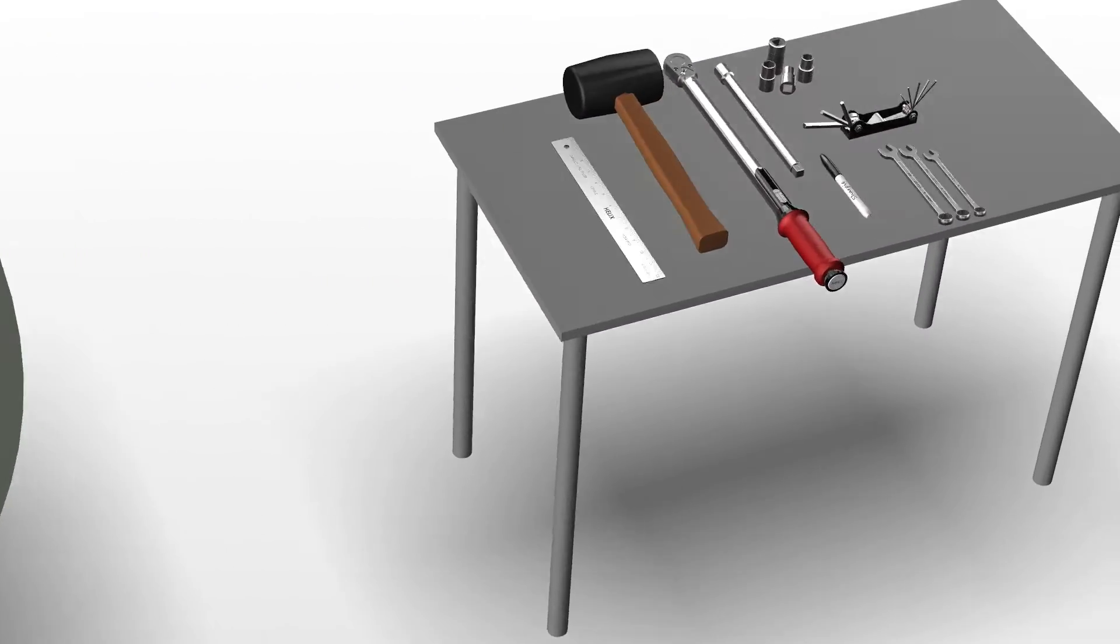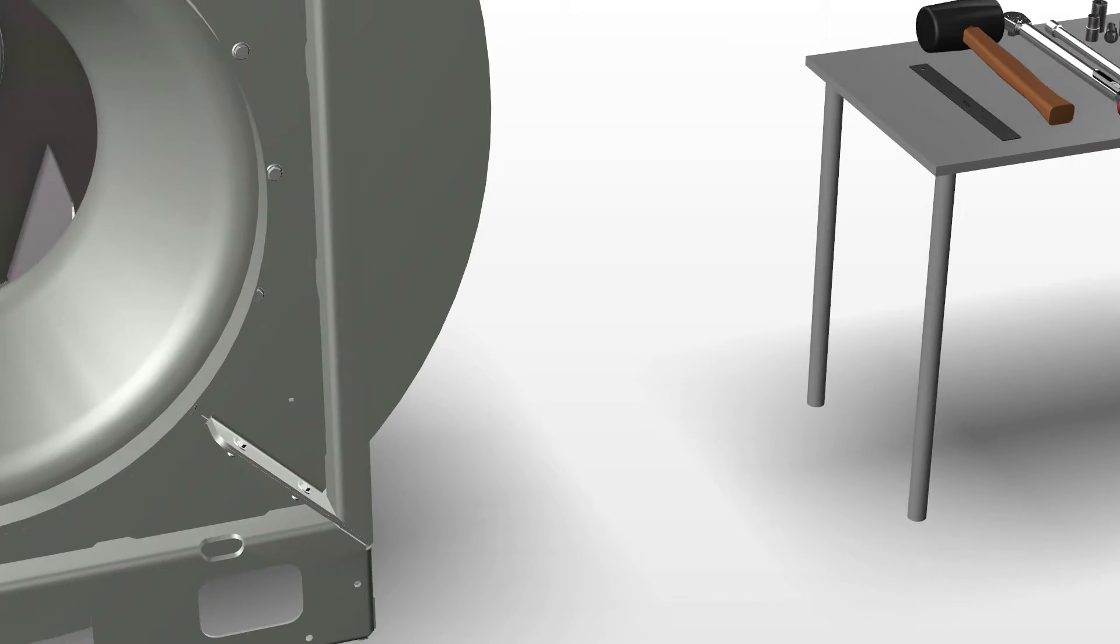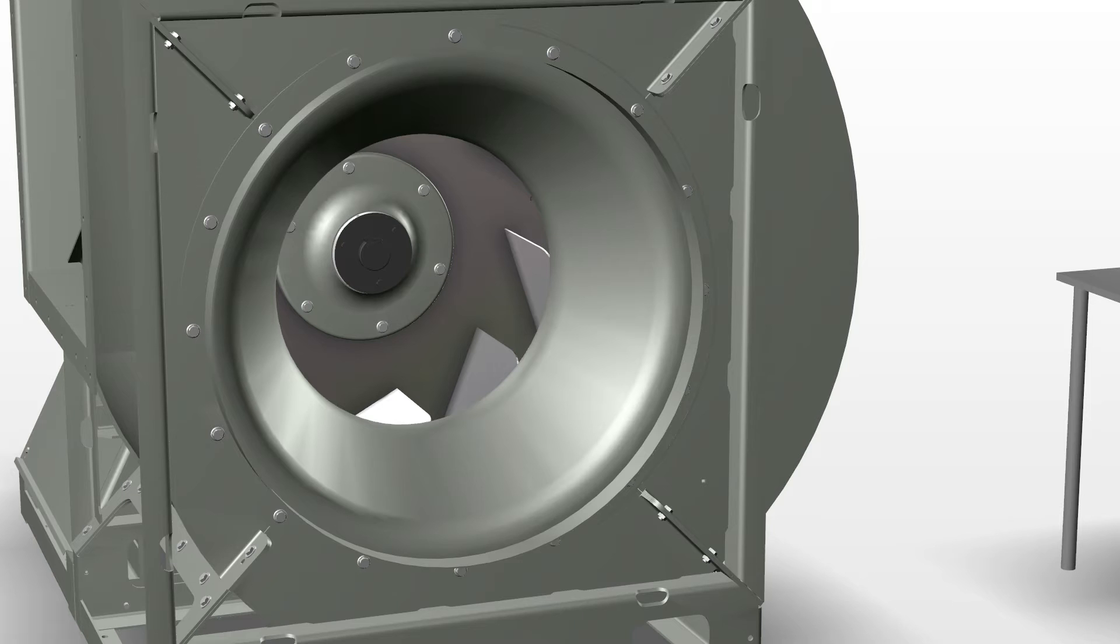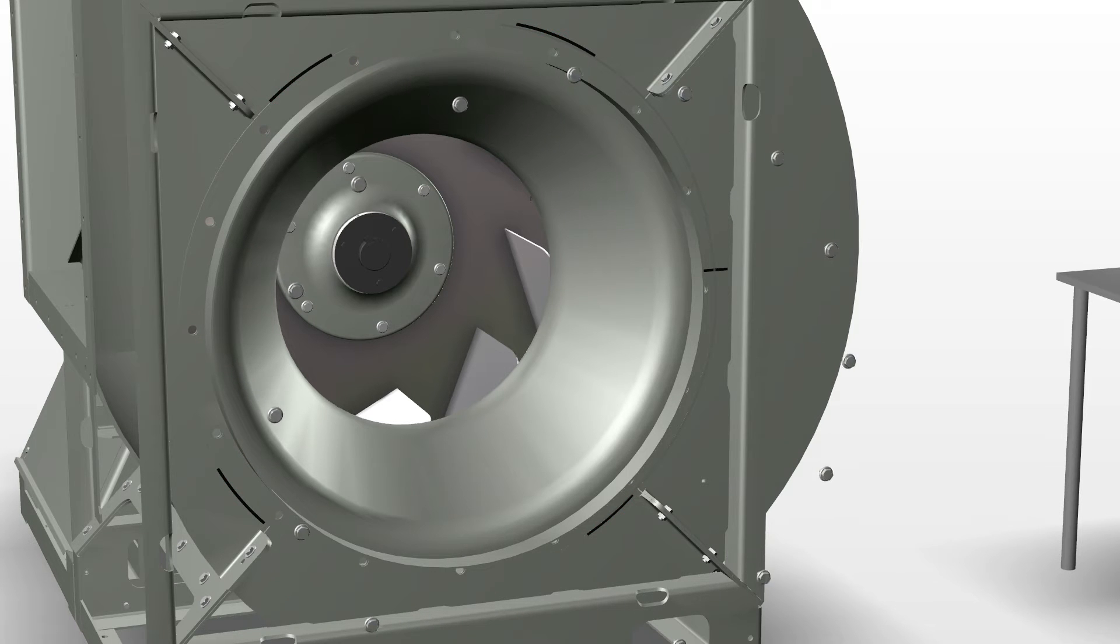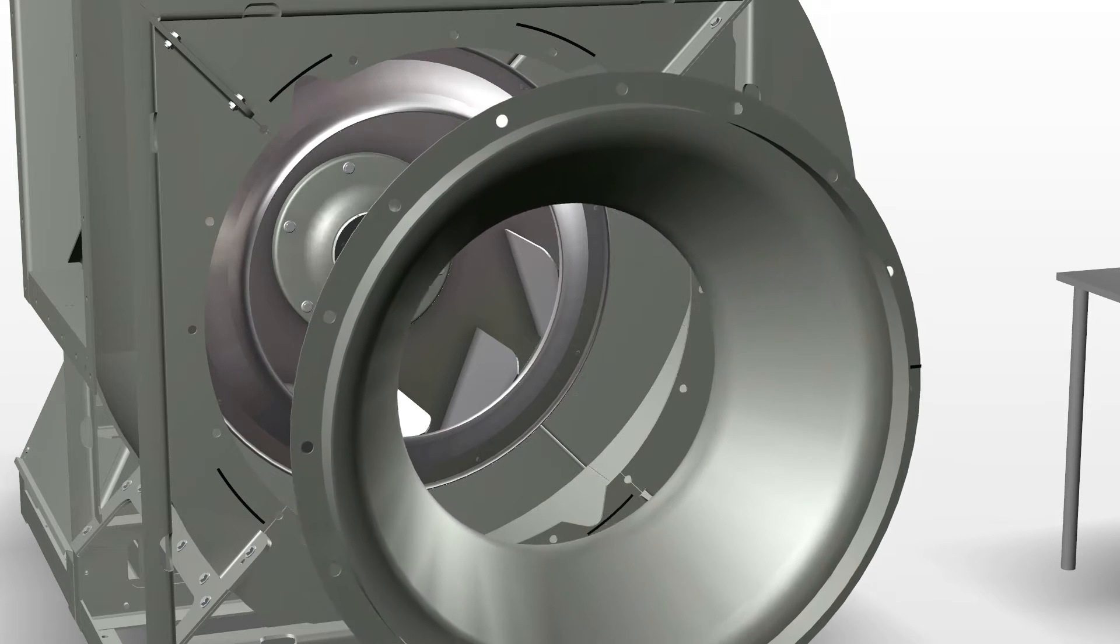Take a marker and go around the cone flange in a few spots for alignment during reassembly. Remove the bolts from the inlet cone and then remove the cone from the fan. The cone may be held in place by foam tape. You may need to pry the cone loose to remove it.